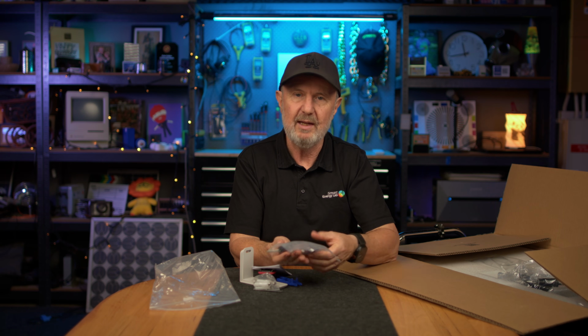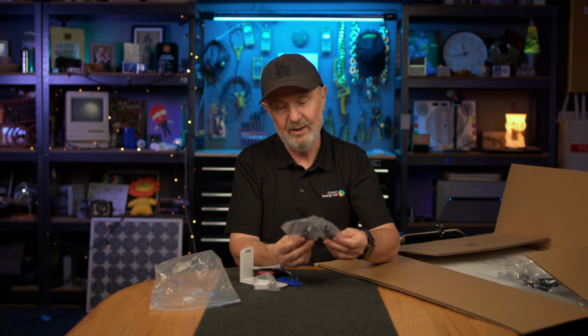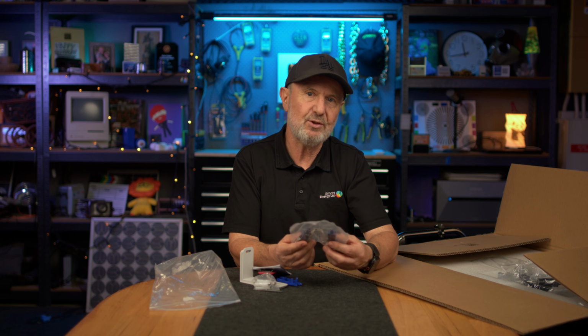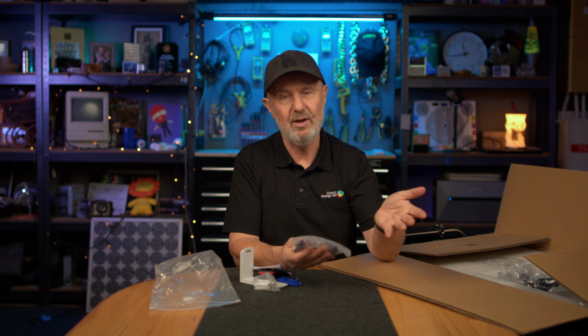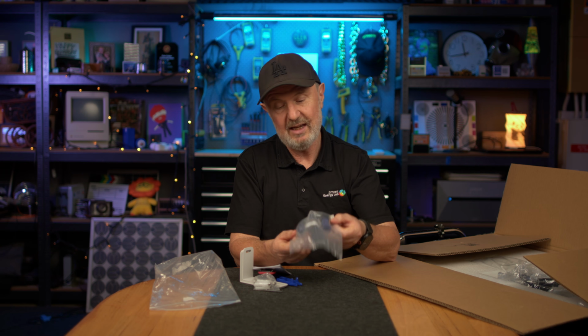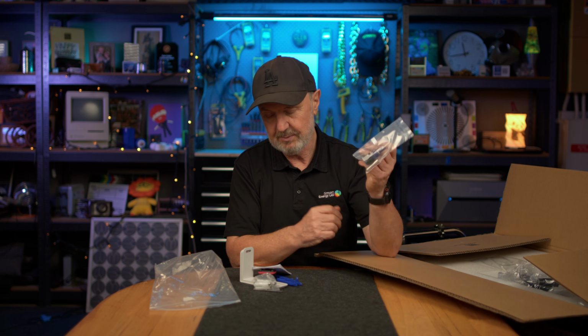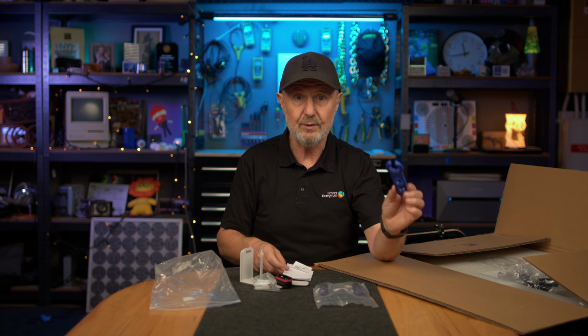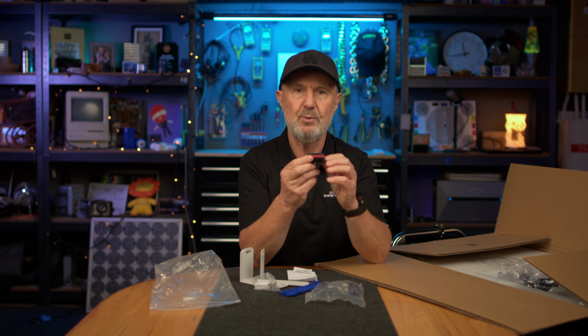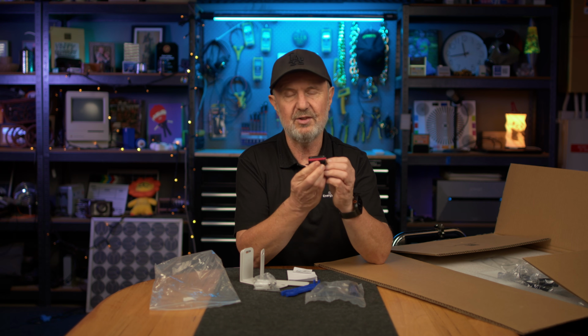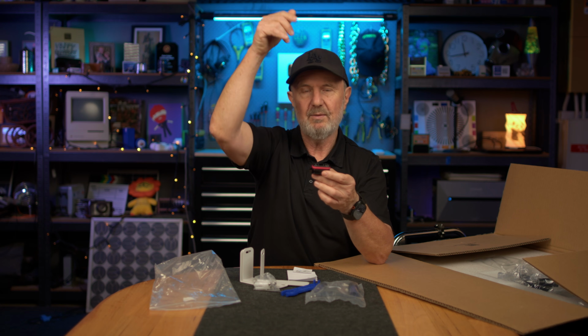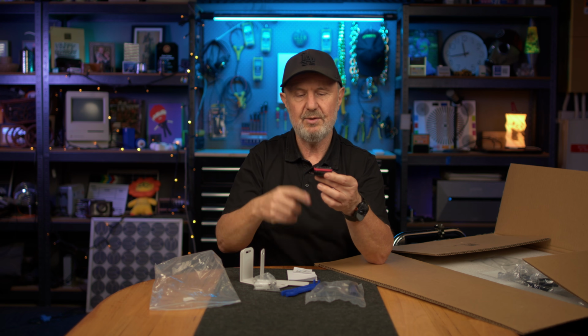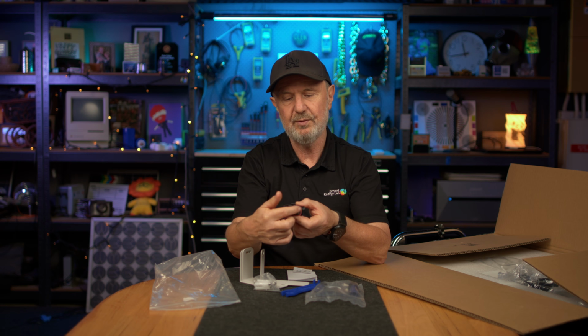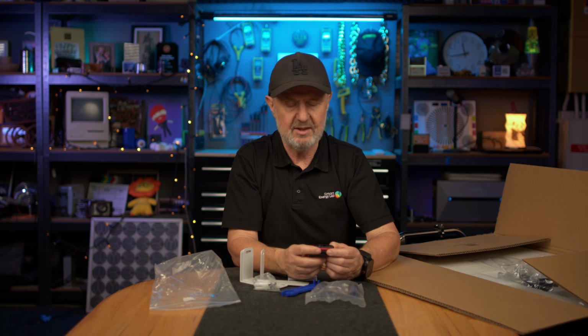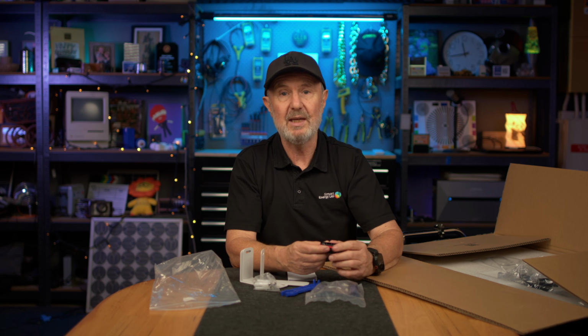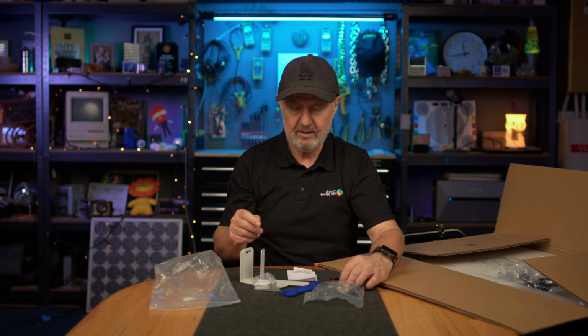I said it was plug and play, but the only thing you might have to do is arrange the cables from the battery, mechanically protect them as required, and put the battery connectors on the end of that cable. So it's a crimp connection, and it comes with the tool for unlocking it. It also comes with the connector at the base of the unit. So basically you've got positive coming down through all the battery modules, it goes into this unit here, which reverses it and comes back up the other side. That way you've only got an output on the BMS, there's no internal cabling needed.